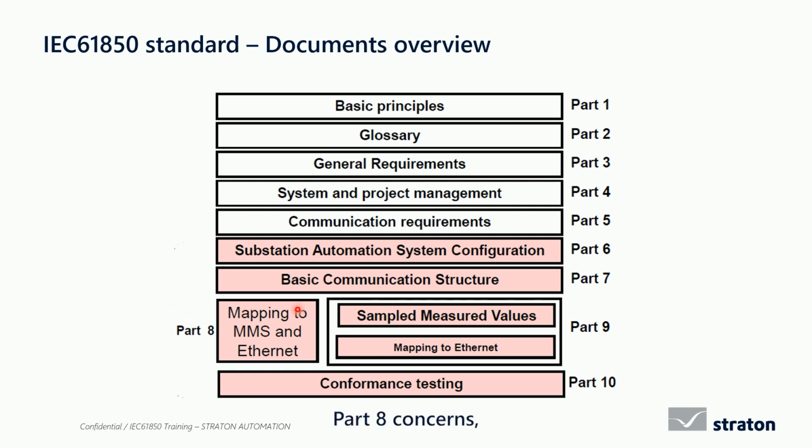Part 8 concerns, among others, the mapping of the IEC 61850 standard over the MMS protocol. We will speak about that later. While making these videos, the released version of Straton is version 10, and part 9 of the 850 standard, sampled measured values, is currently not supported by our 850 server. Finally, Part 10 contains details about the conformance tests to be run if we want our client or server to be compliant with the standard.